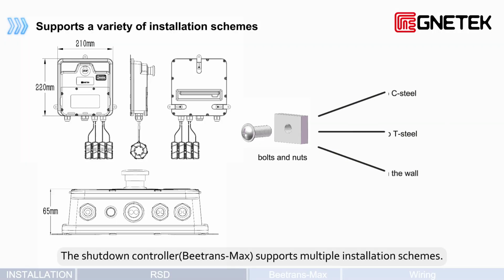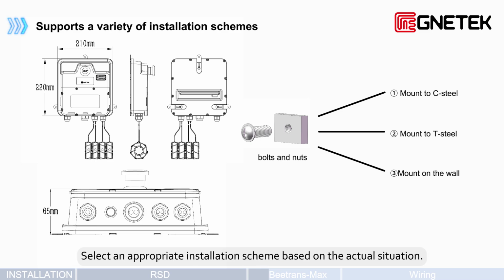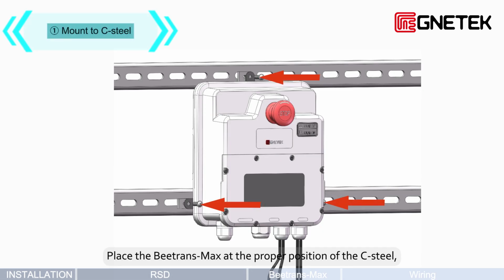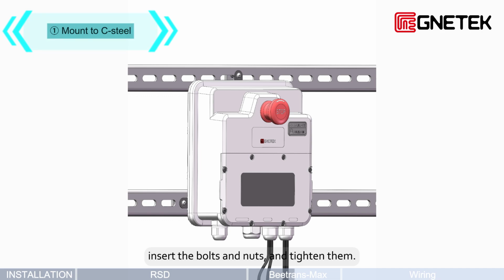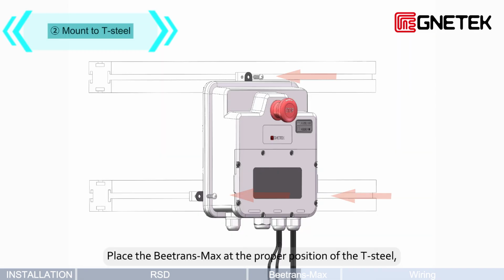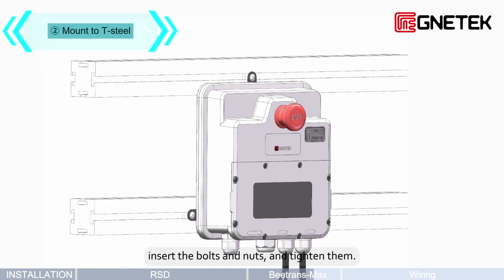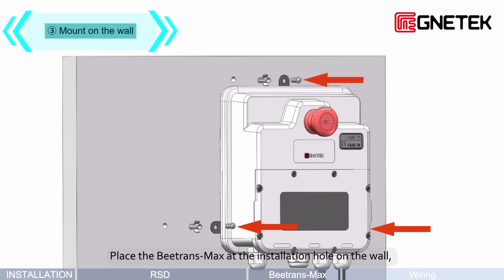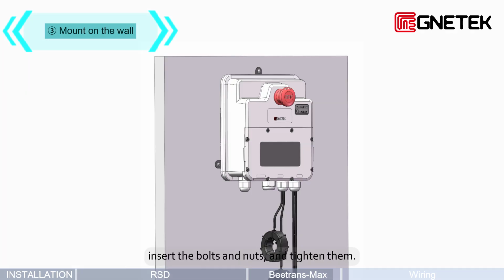The shutdown controller, Beetrans-Max, supports multiple installation schemes. Select an appropriate installation scheme based on the actual situation. Place the Beetrans-Max at the proper position of the C-steel, insert the bolts and nuts, and tighten them. Place the Beetrans-Max at the proper position of the T-steel, insert the bolts and nuts, and tighten them. Place the Beetrans-Max at the installation hole on the wall, insert the bolts and nuts, and tighten them.